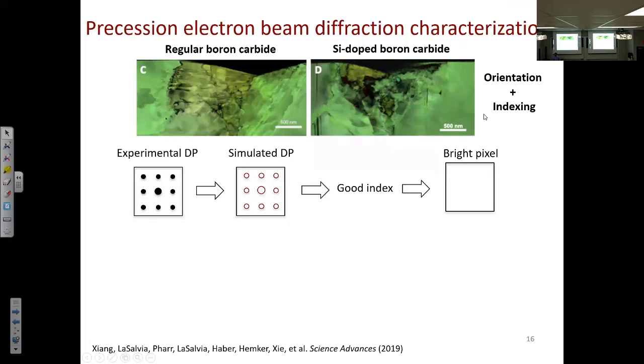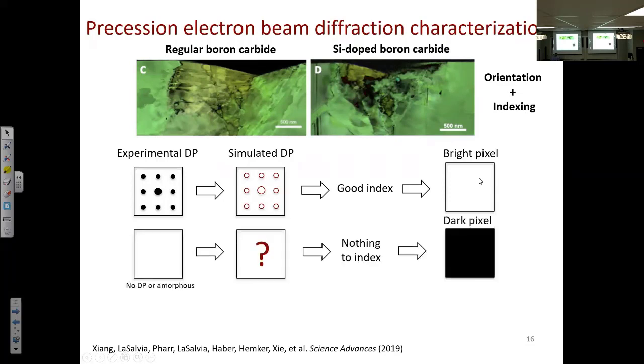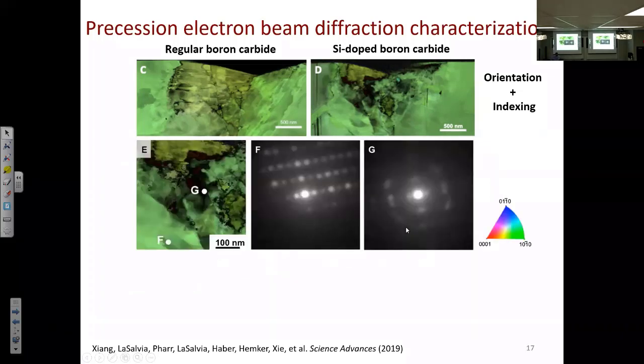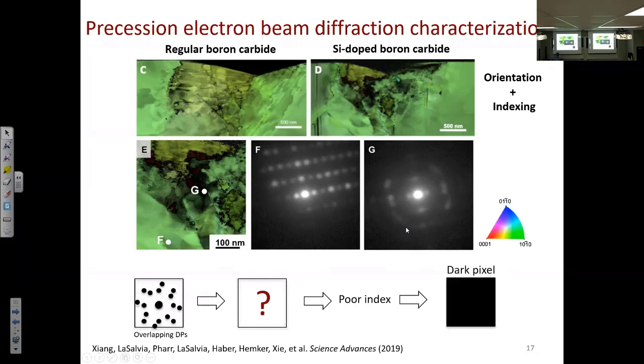Index mapping works as follows: when the experimental diffraction matches the simulated database well, the pixel appears bright. If there is a crack — no diffraction pattern — or amorphous phase — only a diffuse ring — the computer cannot find a matching template and the pixel appears dark. If two sets of diffraction patterns overlay, the computer is again confused and the pixel appears dark. So dark regions indicate cracks, amorphous phase, or crystal overlaps.